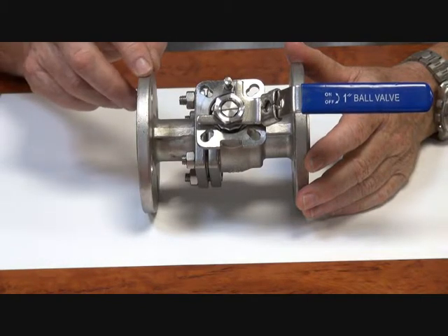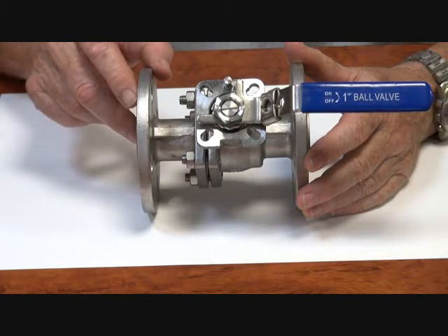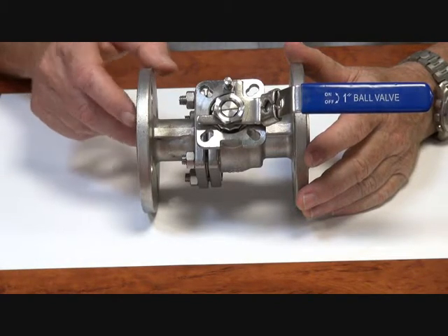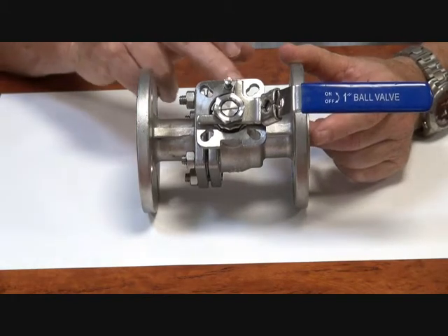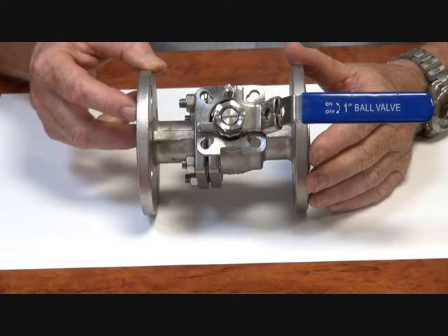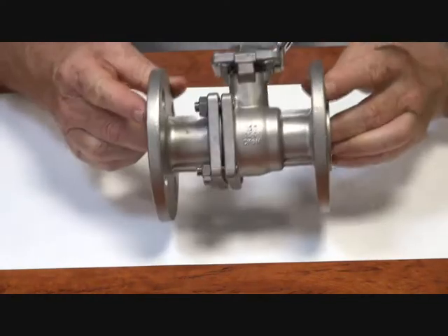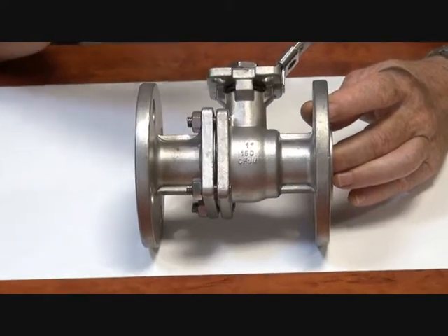The units are two-piece stainless steel 316. They have an ANSI 150 flange. The flange on the top is an ISO interface — a standard interface. The units themselves have RTFE seats, which is a reinforced Teflon seat with glass filled, and in the stem we have a Belleville washer.